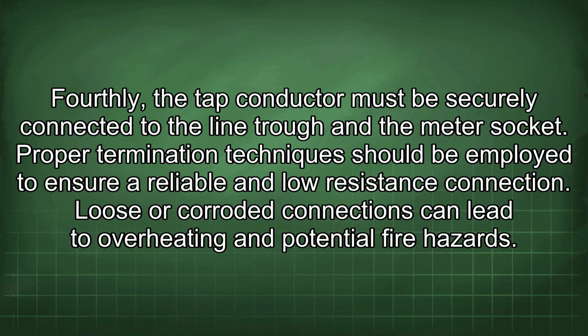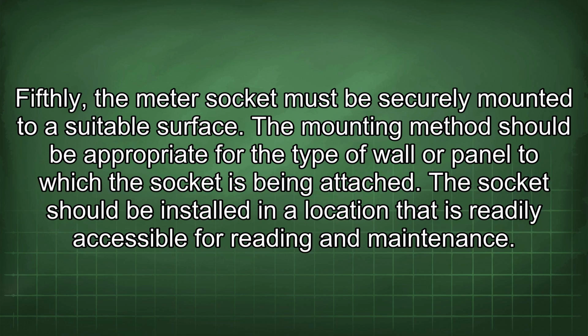Fourthly, the tap conductor must be securely connected to the line trough and the meter socket. Proper termination techniques should be employed to ensure a reliable and low resistance connection. Loose or corroded connections can lead to overheating and potential fire hazards. Fifthly, the meter socket must be securely mounted to a suitable surface. The mounting method should be appropriate for the type of wall or panel to which the socket is being attached. The socket should be installed in a location that is readily accessible for reading and maintenance.